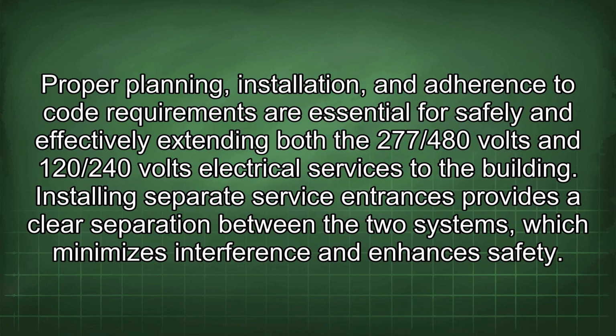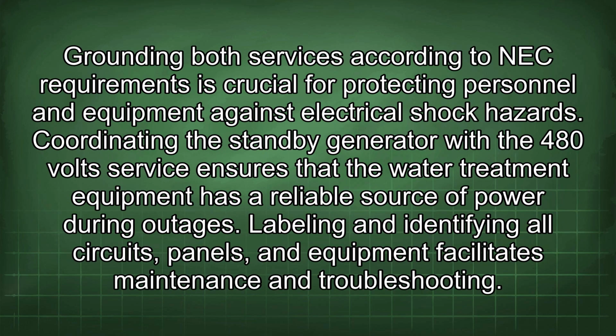Proper planning, installation, and adherence to code requirements are essential for safely and effectively extending both the 277/480 volts and 120/240 volts electrical services to the building. Installing separate service entrances provides a clear separation between the two systems, which minimizes interference and enhances safety. Grounding both services according to NEC requirements is crucial for protecting personnel and equipment against electrical shock hazards. Coordinating the standby generator with the 480-volt service ensures that the water treatment equipment has a reliable source of power during outages. Labeling and identifying all circuits, panels, and equipment facilitates maintenance and troubleshooting.